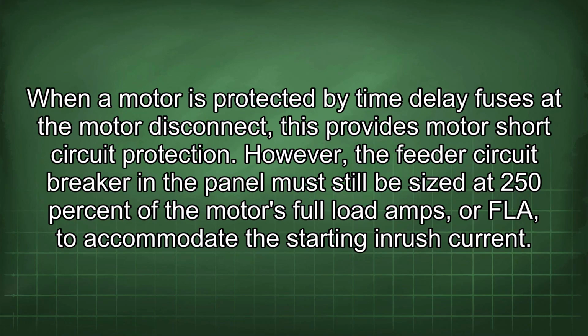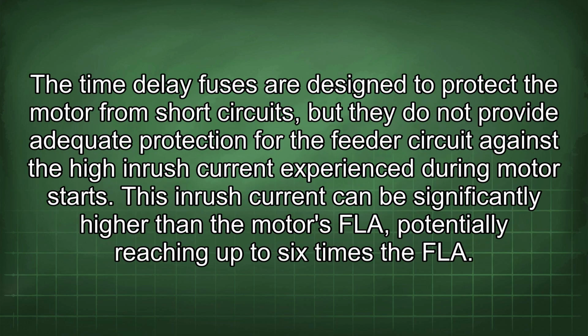When a motor is protected by time delay fuses at the motor disconnect, this provides motor short circuit protection. However, the feeder circuit breaker in the panel must still be sized at 250% of the motor's full load amps, or FLA, to accommodate the starting inrush current. The time delay fuses are designed to protect the motor from short circuits, but they do not provide adequate protection for the feeder circuit against the high inrush current experienced during motor starts.